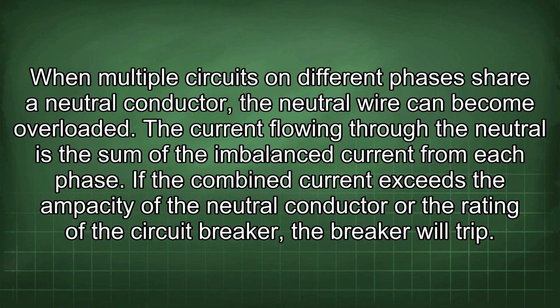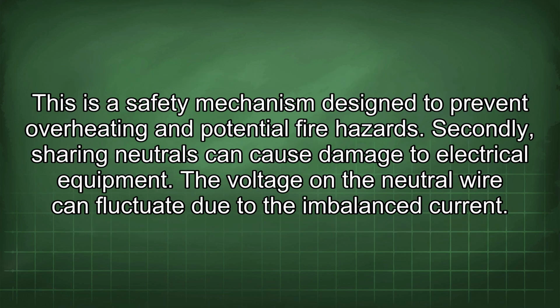When multiple circuits on different phases share a neutral conductor, the neutral wire can become overloaded. The current flowing through the neutral is the sum of the imbalanced current from each phase. If the combined current exceeds the ampacity of the neutral conductor or the rating of the circuit breaker, the breaker will trip. This is a safety mechanism designed to prevent overheating and potential fire hazards.